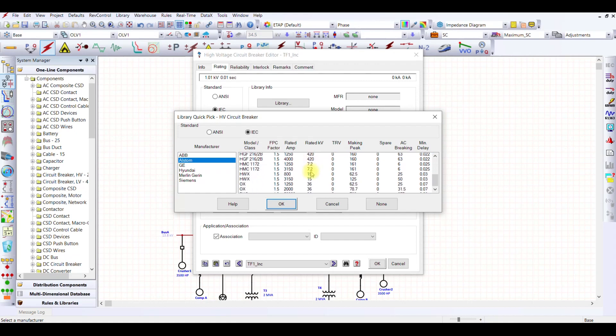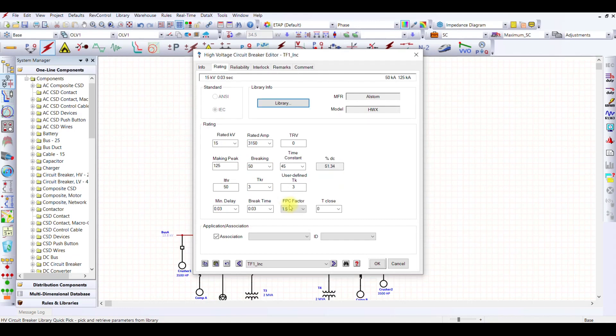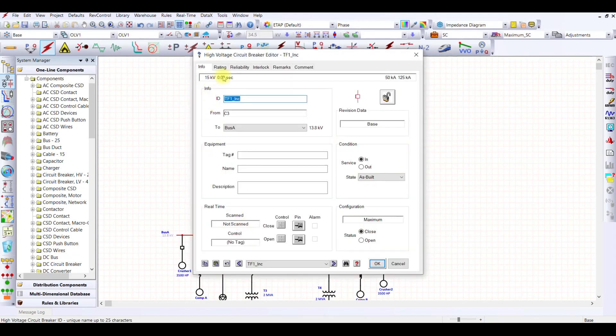In Alstrom we have big breakers. 15 kV breaker is there with a capability of 25 kilo ampere and 50 kilo ampere. 25 kilo ampere won't work for me, so I will have to use 50 kilo ampere. When I press, 50 kilo ampere. What is the name of this breaker? I have Alstrom HWX model.